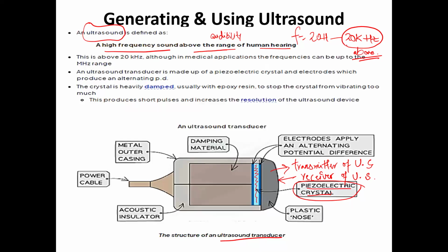So what will happen in this specific case? The piezoelectric crystal is embedded between electrodes, and the electrodes are generally silver metal plates. The dark blue ones, on the right side and the left side, are both made of silver. So the piezoelectric crystal is embedded in between the silver metal plates.